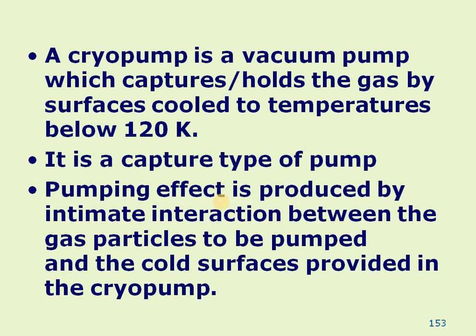At low temperatures, when certain surfaces are maintained at cryogenic temperatures, gas molecules impinge on the surface. The energy is suddenly taken by the cryo surface — once the energy is taken from a gas molecule, its vibration and oscillation frequency get reduced. Ultimately they get deposited on the surface; their kinetic energy is lost, they freeze and stop on the surface.